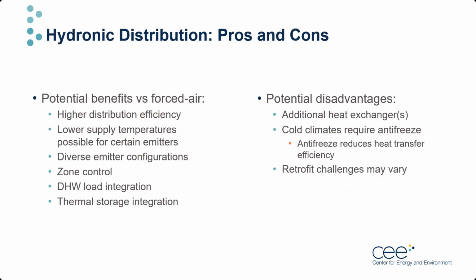But first, let's touch on the pros and cons of using hydronic distribution. There are many reasons you might want to pair an air source heat pump with a hydronic distribution loop. For one, the heat capacity of water is way higher than air. It can hold more than 3,500 times as much energy as the same volume of air, and that means you don't have to spend so much energy moving it around for the same heat output. Modern hydronic emitters are also compatible with lower supply temperatures, and that includes radiant flooring. Reducing supply temperature requirements can in turn improve the efficiency of the heat pump cycle. In addition to this, air-to-water heat pumps can provide a ton of flexibility as well, with diverse emitter configurations, zone control, and even potential for integration with domestic hot water and with thermal energy storage.